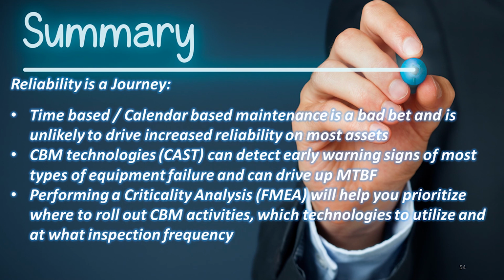So summarizing: time-based, calendar-based maintenance is a bad bet, at least three-quarters of the time - probably higher, probably 90% of the time. The only time calendar-based maintenance makes sense is on circuit breakers themselves, because the OEMs have done their homework and can tell you what to do, and I trust them with respect to those recommendations. All other recommendations they make, I'm pretty skeptical about.